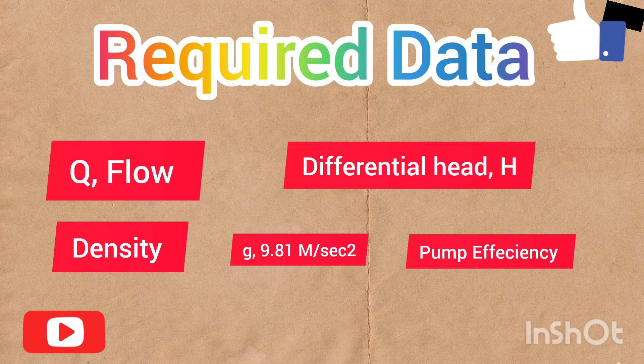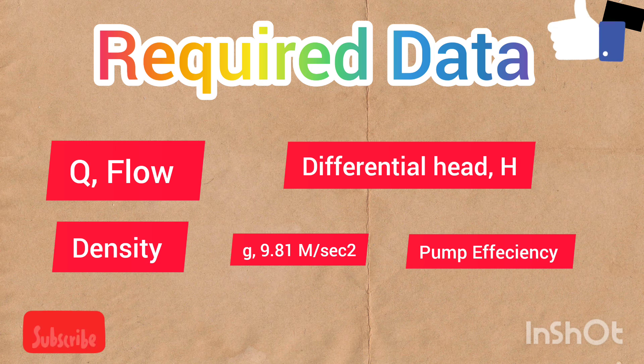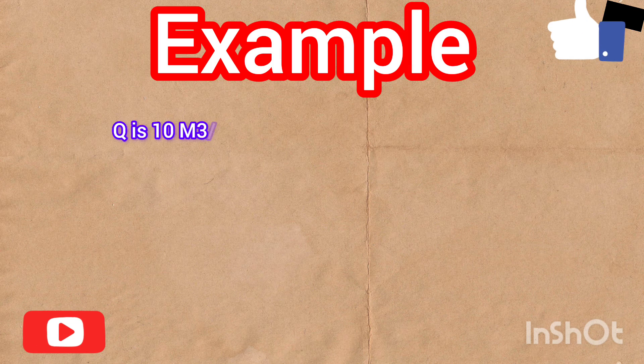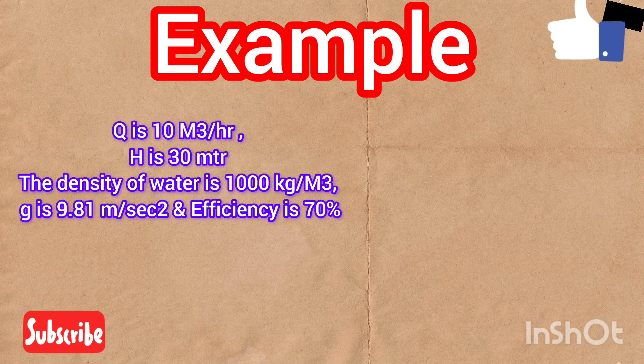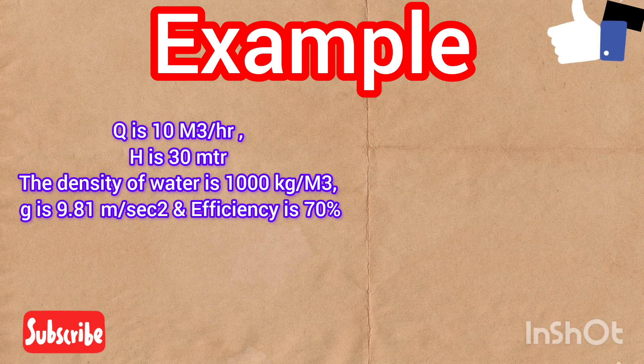Let's start with an example. Assume Q is equal to 10 meter cube per hour and differential head is 30 meters. The density of water is 1000 kg per meter cube and we assume pump efficiency is 0.7. If you don't have the pump efficiency, you need to ask the pump vendor.